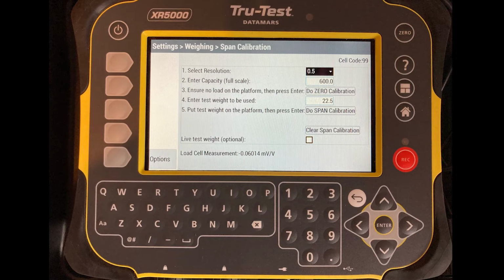If you still find your weigh crate is weighing inaccurately after you've checked there's nothing giving you an issue with the load cells working properly, you could always do a recalibration of your load cells to your weigh head. This is called a span calibration. The span calibration can be done by weighing the weigh crate empty, then putting a predetermined weight inside the weigh crate and recording that on the weigh head. This will recalibrate your weigh head to know what resistance it's feeling. Span calibrations are also done when using unipart weigh cells made by other manufacturers than Tru-Test. Tru-Test do have a list in their XR5000 of other manufacturers' weigh cells which you can convert across.